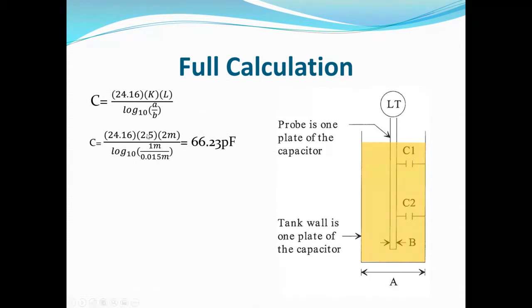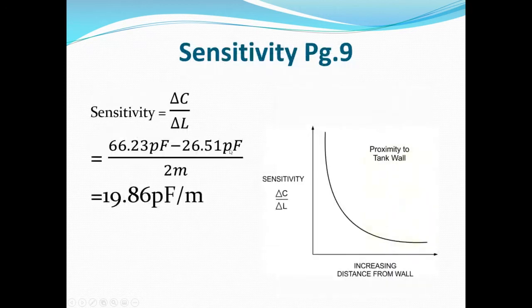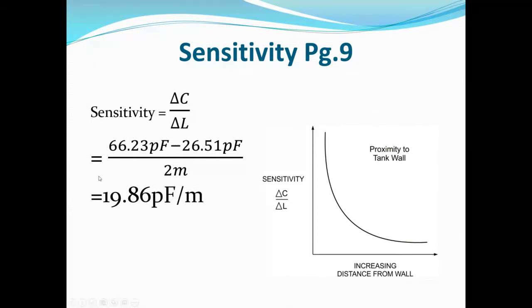The sensitivity formula is the change in capacitance over the change in length. With a full capacitance value of 66 picofarads and an empty value of 26 picofarads, subtracting those two and dividing by the 2-meter probe length gives a sensitivity of 19.86 picofarads per meter.